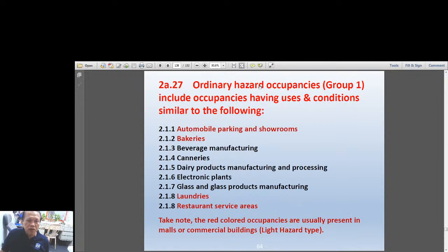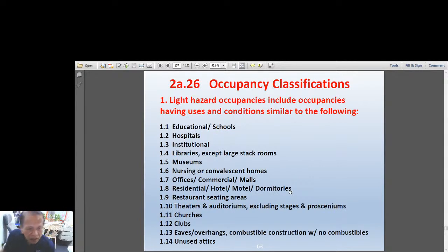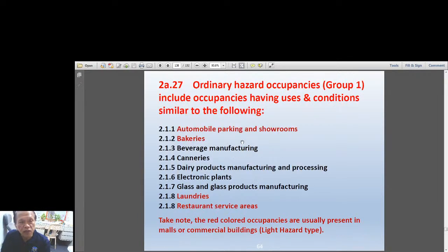The next is ordinary hazard. But take note, in the ordinary hazards, there are several items that usually are in our present buildings, like in malls. In malls, we have parking. This one, parking. And we have bakeries there, no? Sometimes you also have laundries. Okay? And they have plenty of restaurants. So therefore, in the first type, which is the light hazard type, like light hazard for commercial or malls, if you have a parking, that would upgrade it therefore to ordinary hazard type.